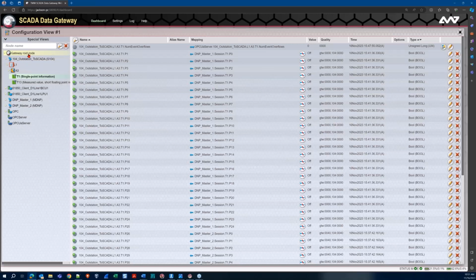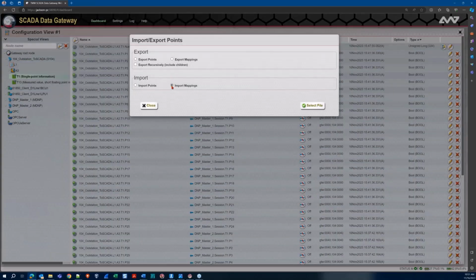That alternative method is to import a mapping file. This looks a lot like importing and exporting points before, but instead of just creating points on a particular device, importing mappings clarifies where on the other device the point needs to be connected. So if you have a spreadsheet that defines your gateway's functionality and what data needs to be available at what point, you can leverage something like Excel, export some initial mappings, merge them with your descriptor file's mappings, create the mapping for the entire gateway there, and then import it back up here. That's particularly useful if you already have documentation defining how your gateway should work and what points map where.